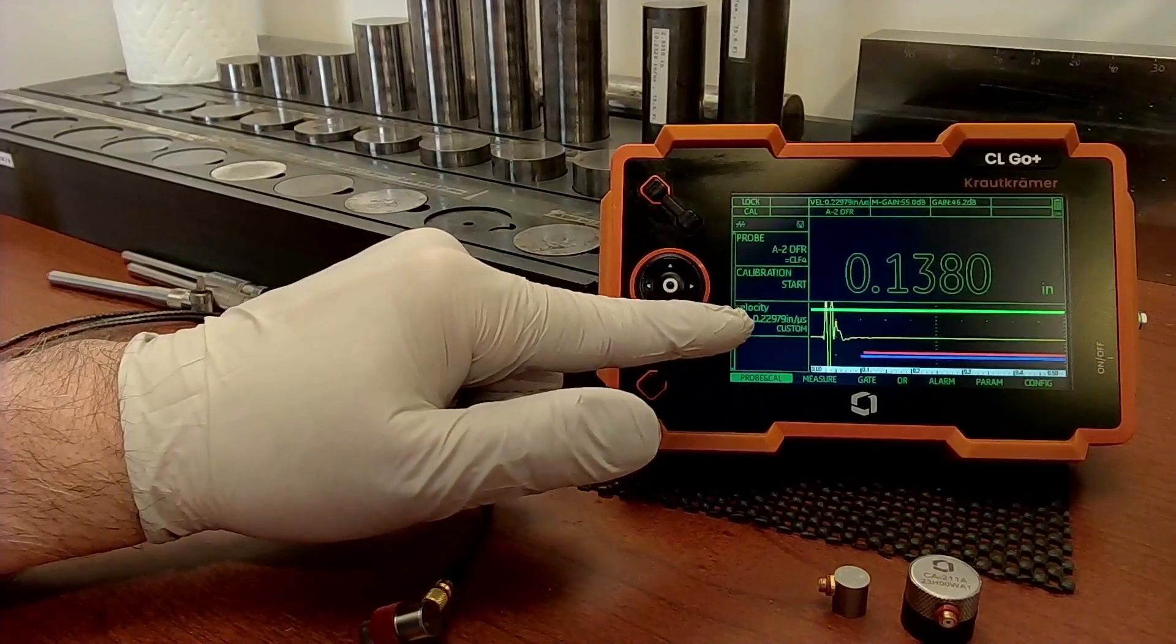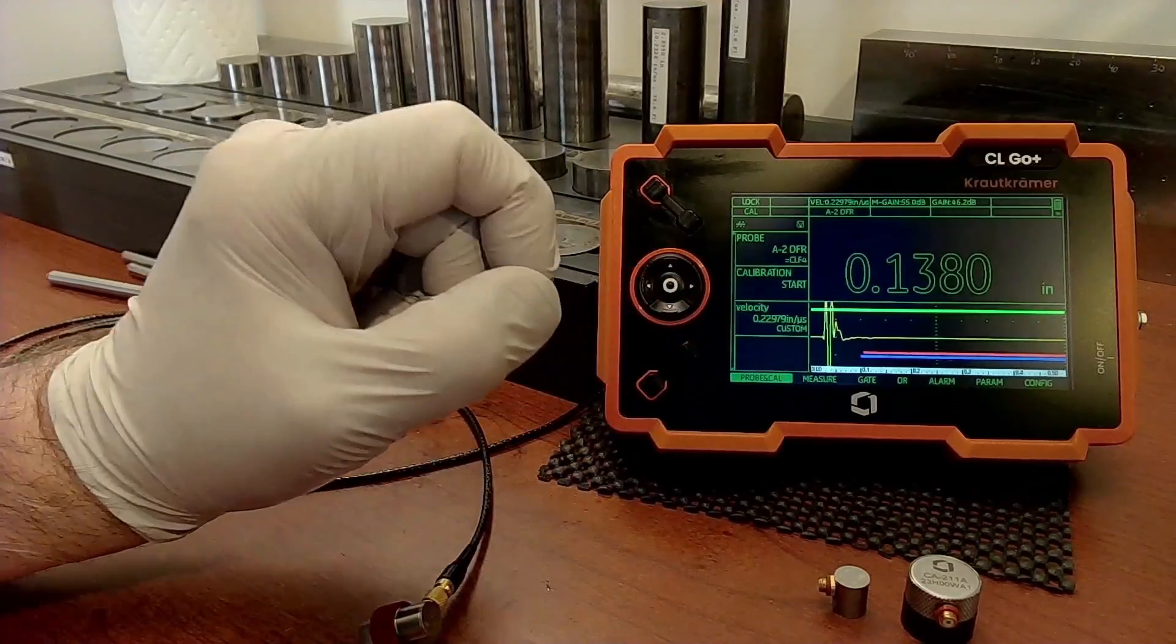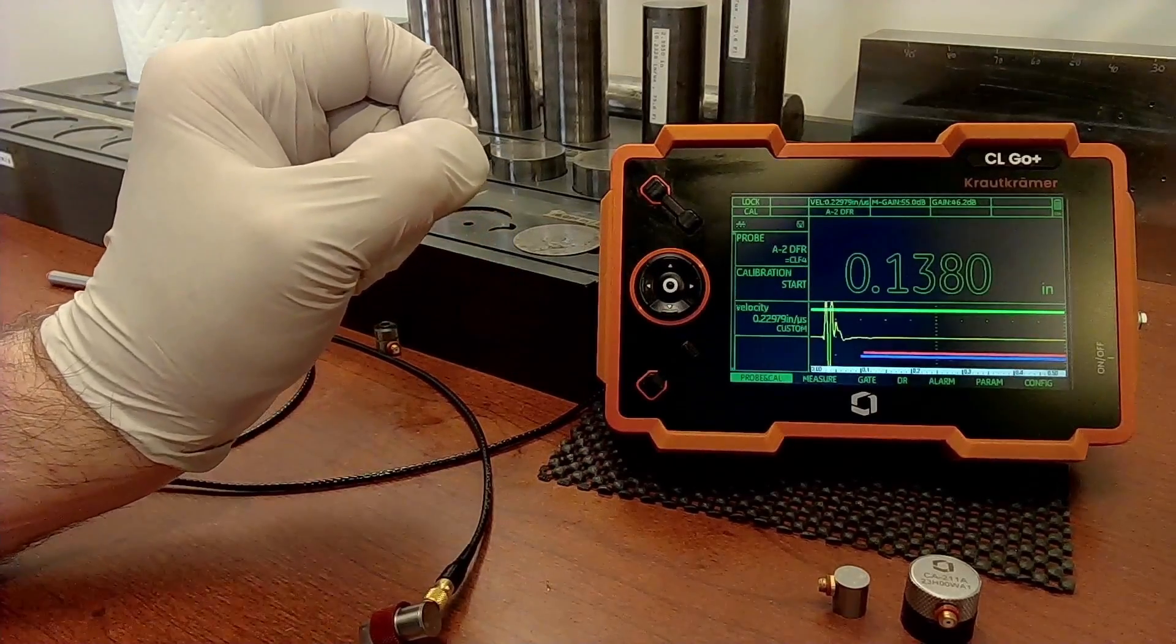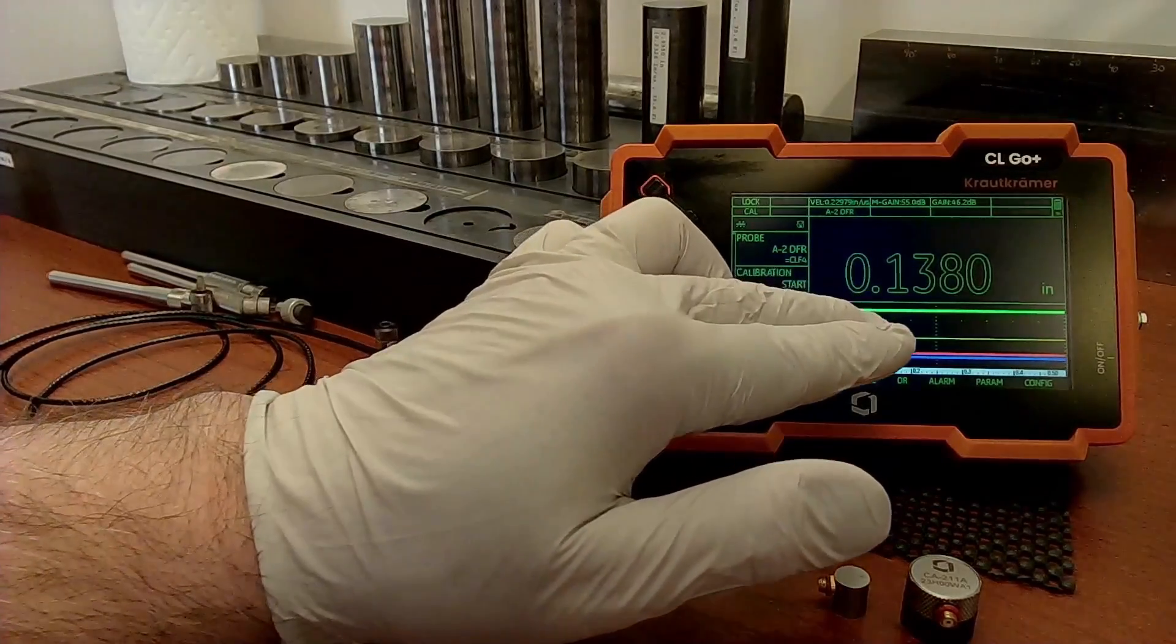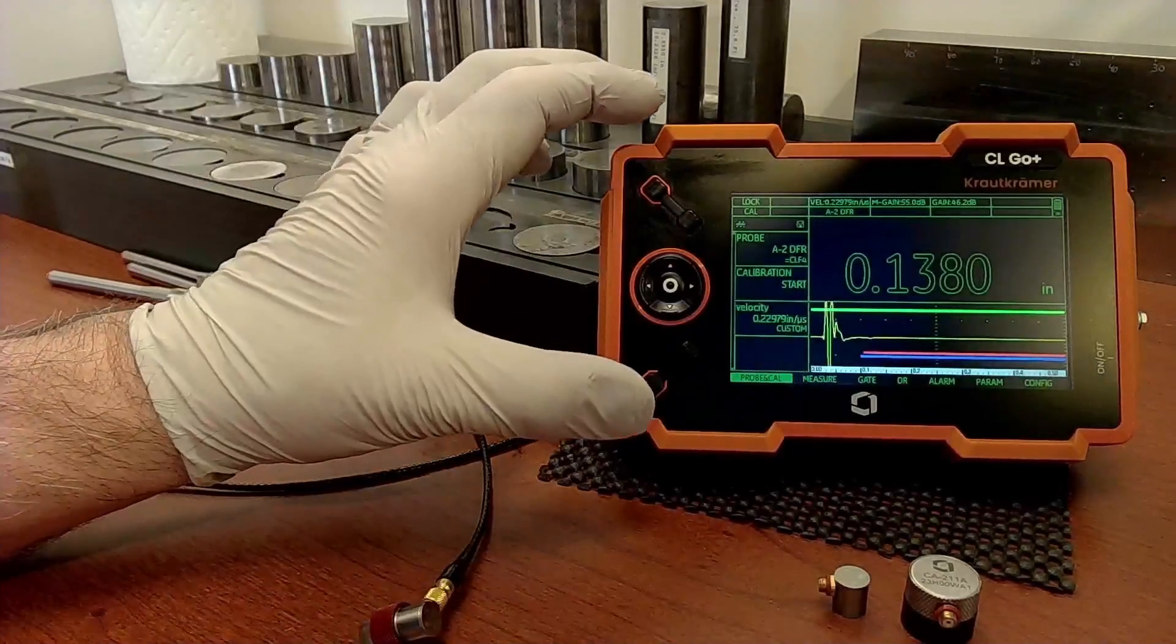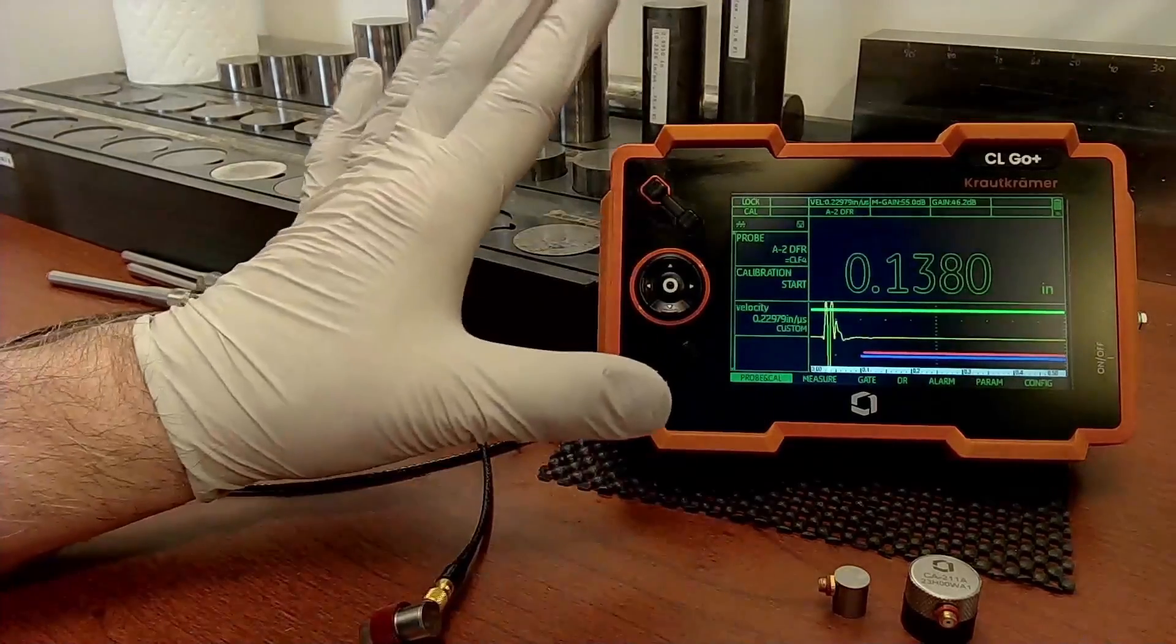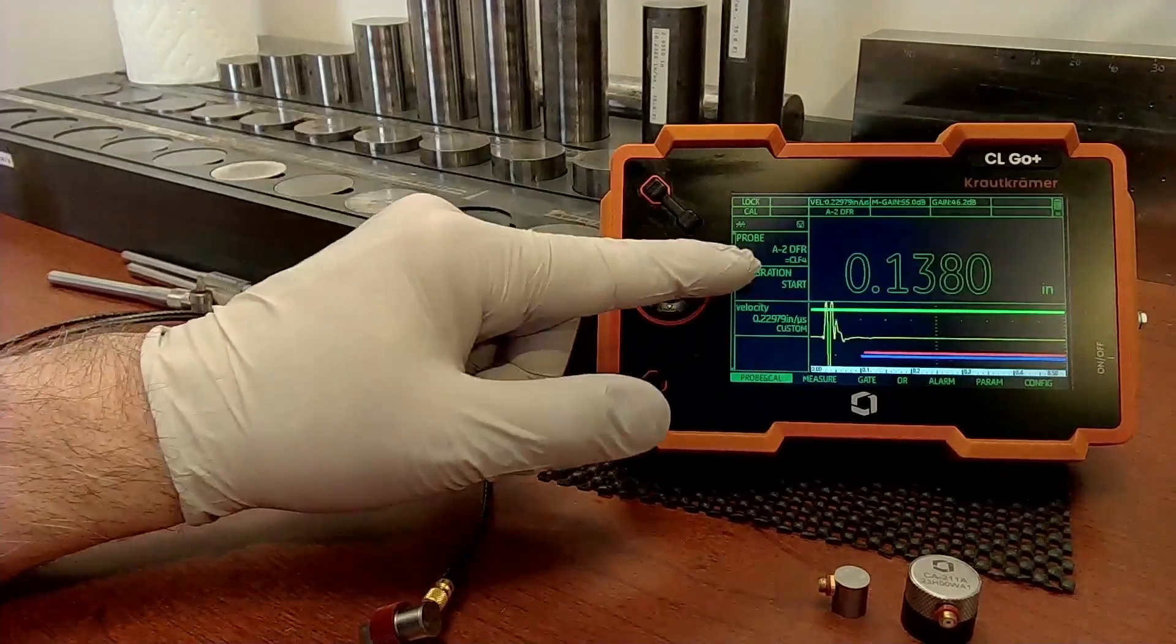Right now I'm working with the simplified menu set. On the CL Go we have all of the options and setup capabilities that would be familiar to a user of the DMS Go. So we have a very robust set of controls around gate positions, gain control, things like that. The instrument can be kept in a very simple operating mode. And we can hide almost all of that complexity. In this simplified mode, we call it inspector mode.